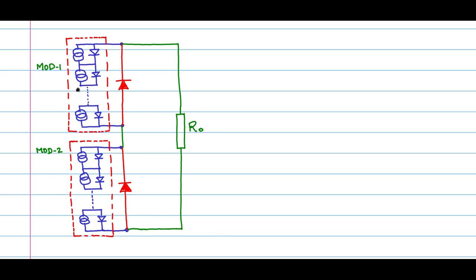Whichever of the modules has shading and starts to or tries to go to the sink zone of operation, the bypass diode will come and protect them, effectively removing that portion of the module out of the circuit. However, you should know that within the module there are cells in series.